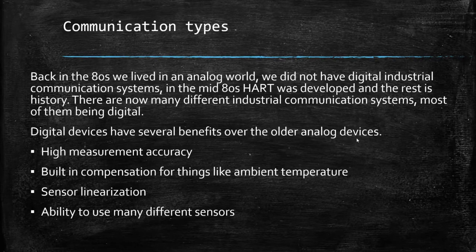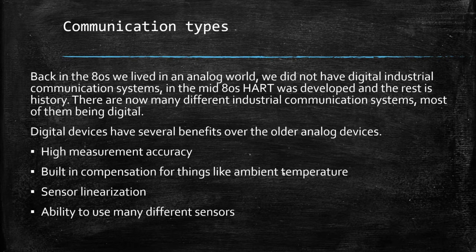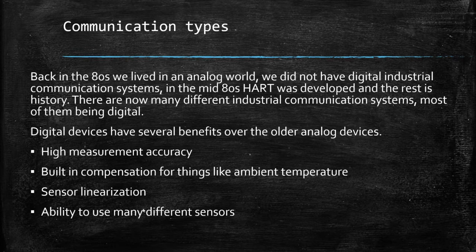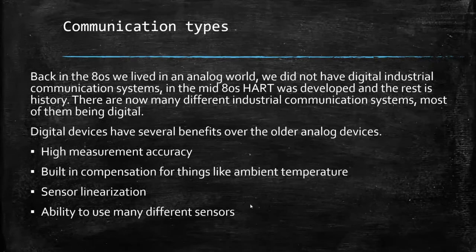Digital devices have several benefits over the older analog devices. They have higher measurement accuracy, usually in the order of 10 times more accurate. They have built-in compensation for things like ambient temperature and other variables. They have the ability to do linearization — or characterization — on their sensors and outputs. They can use many different sensors; like a Rosemount transmitter, the transmitting portion could use temperature sensors, pressure sensors, and different types. Some analyzers can do pH, conductivity, ORP — all from the same transmitter, just different sensors.